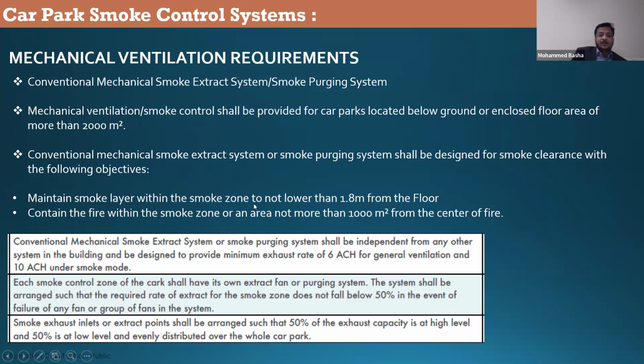Maintain the smoke layer within the smoke zone, not lower than 1.8 meters from the floor. Contain the fire within the smoke zone or an area of not more than 1000 square meters from the center of the fire. This is the only place where they are telling you to use 6 air changes and 10 air changes, because this whole concept is derived from BS 7346.